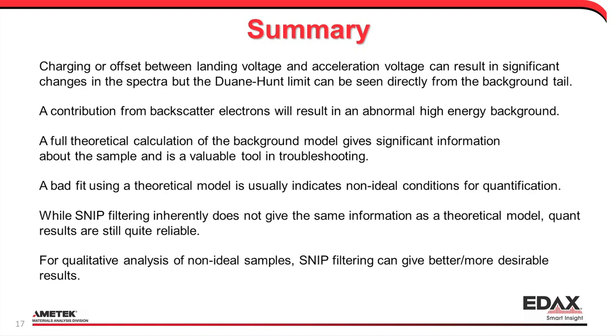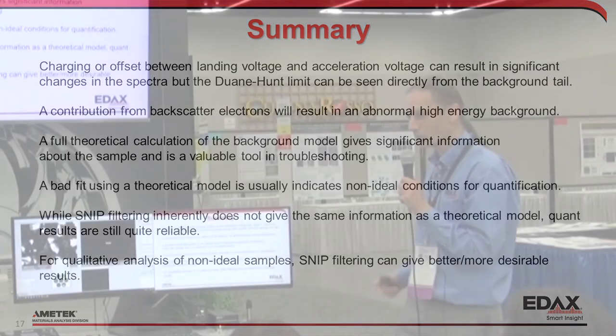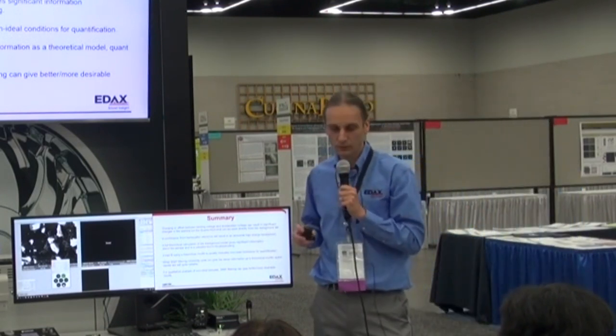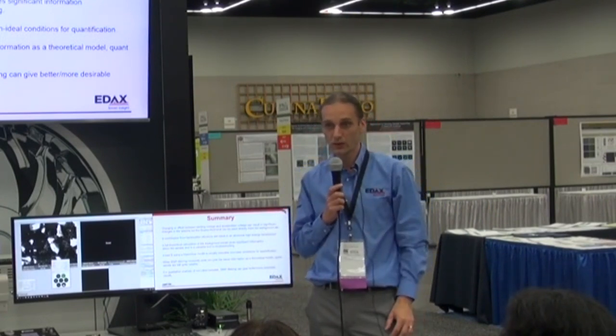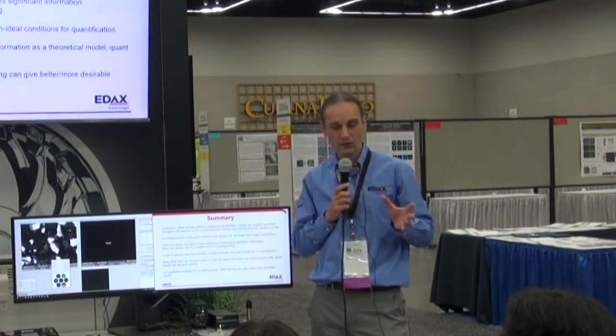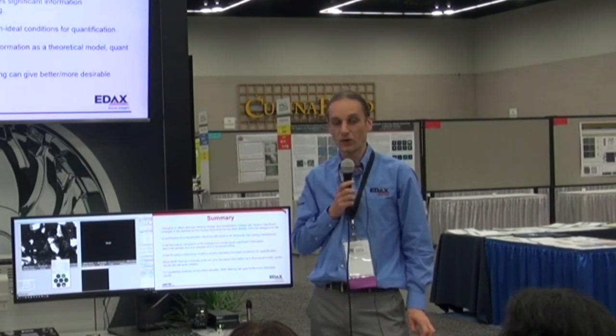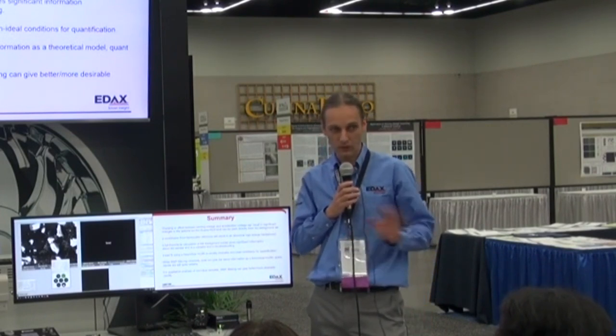If you see a bad fit in the theoretical Bremsstrahlung calculation with one single high energy fit region, that's pretty much an indication you shouldn't click the quant button, or at least not trust the results in a meaningful sense. You can still get a rough qualitative idea of what's in there. The SNIP filter gives you a nice clean curve — it's always nicer to show clean curves when handing data to people — and it can be much better for qualitative analysis on non-ideal samples where you shouldn't do quant anyway. But if you need the SNIP model to get a good fit, don't trust the quant results. You can get good quant results with SNIP, but it all depends on whether the sample meets the requirements for the quantification model.